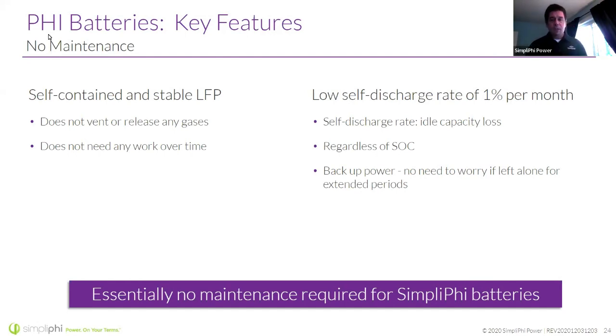you could start to be in those very, very low states of charge. If that were the case and you got a battery that was at a low state of charge and you knew it was going to be a couple months before your project got off the ground, we would just recommend charging it up. If you get that battery fully charged, you can absolutely let it sit. If it's waiting for more than maybe 6 months or a year, maybe give it another charge. But that is not the case with some other batteries, where if you let them sit, the self-discharge rate may be much higher. So no maintenance.